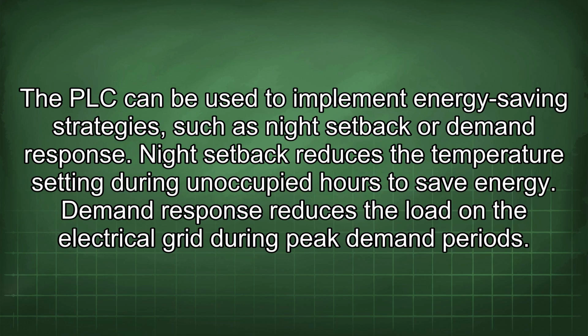The PLC can be used to implement energy-saving strategies such as night setback or demand response. Night setback reduces the temperature setting during unoccupied hours to save energy. Demand response reduces the load on the electrical grid during peak demand periods.